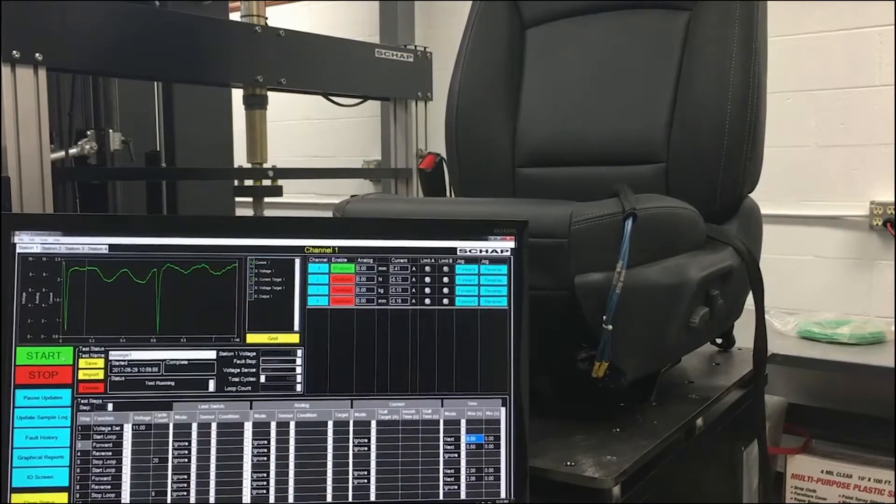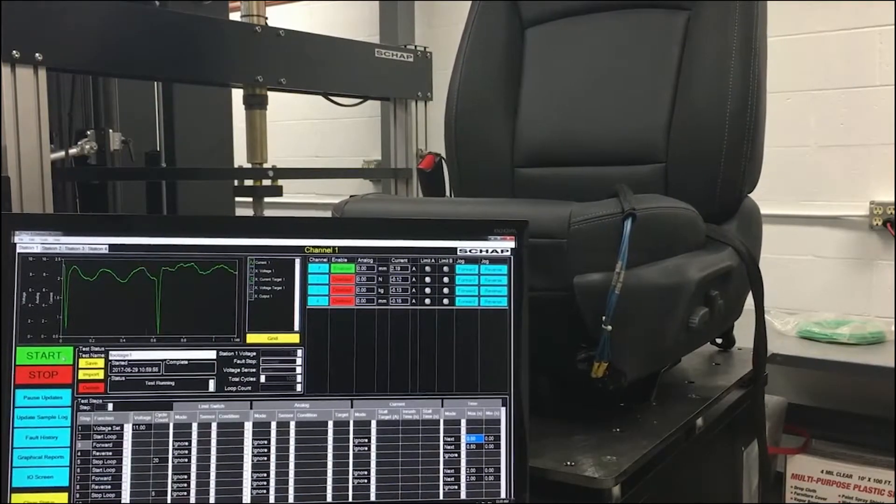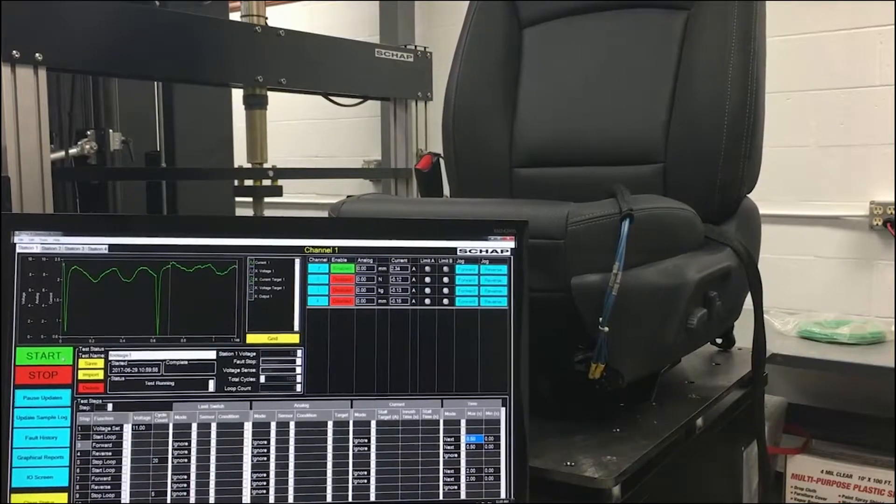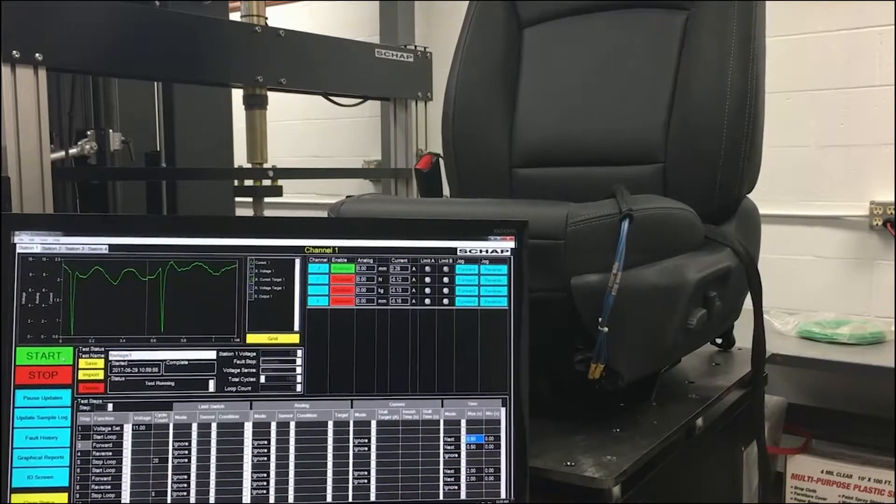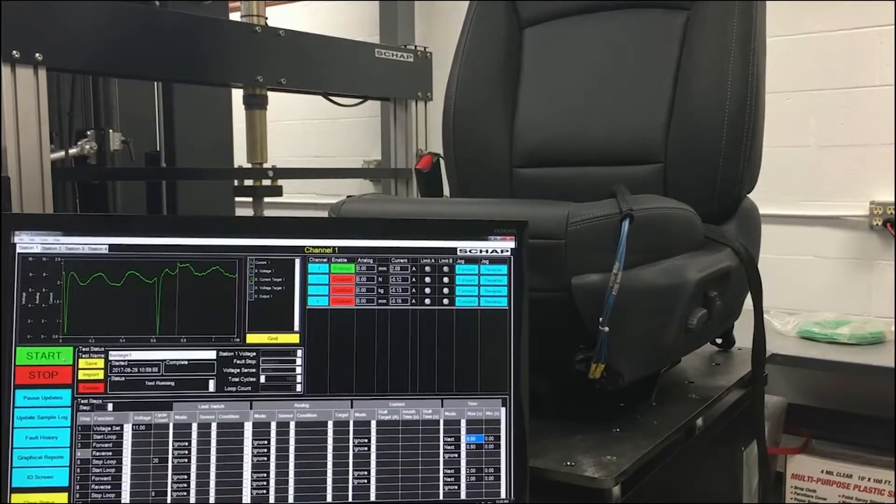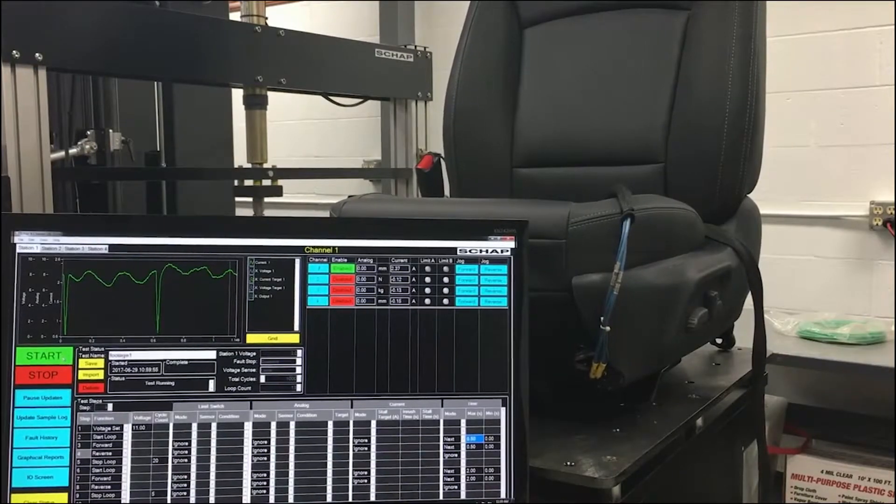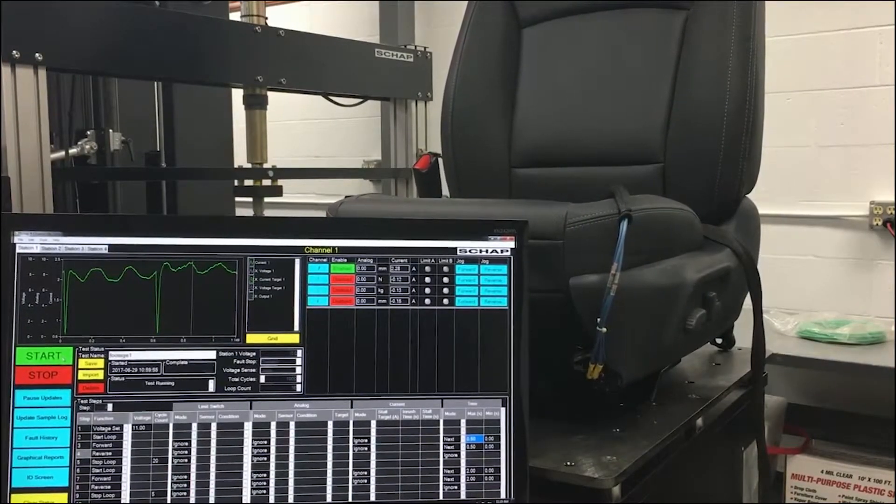These three values should be entered. The stall target defines the current in amps at which the motor should be considered to have stalled. This should be larger than any spikes in the steady state current.